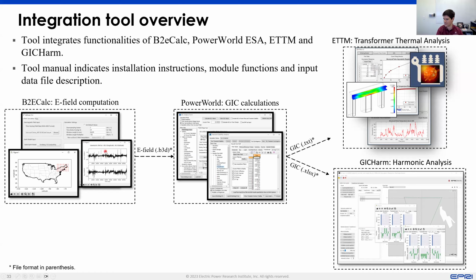The goal, and what we've demonstrated, is that instead of doing all three pieces separately, manually loading files from PowerWorld into GIC Harm for every single transformer, it can be done with the push of one button in PowerWorld, running a GMD analysis, a harmonic analysis, and a thermal analysis all at once for all your transformers.